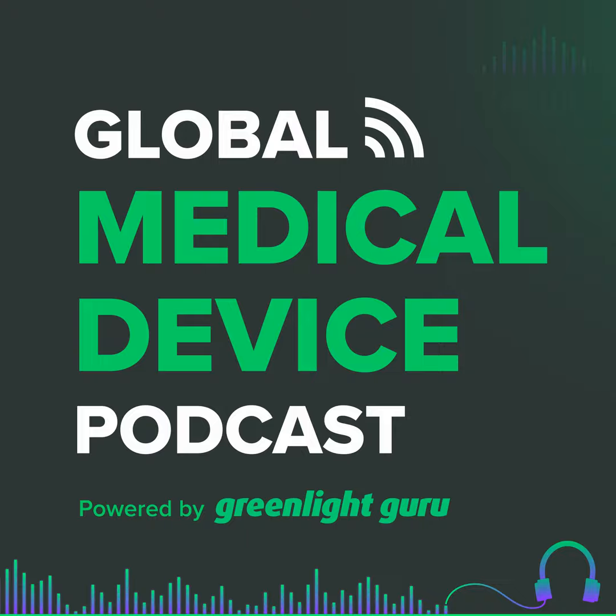So reason number one that I recommend bringing NSR devices to the FDA, I don't bring it just as a standalone NSR question, but I usually embed it in an existing pre-sub, is to make sure that FDA sees it also as a non-significant risk device. Because if they don't see it as a non-significant risk and you submit your 510K or de novo or whatever it is later on, now you're in a whole bunch of problems and you haven't even started talking about your device yet. That problem doesn't happen an awful lot, but it does happen from time to time.